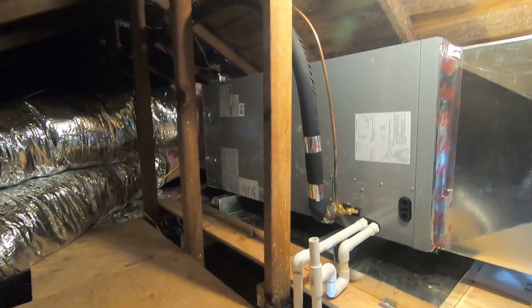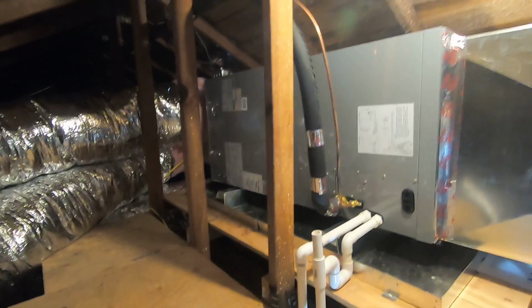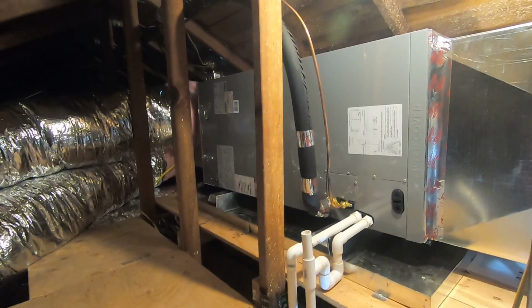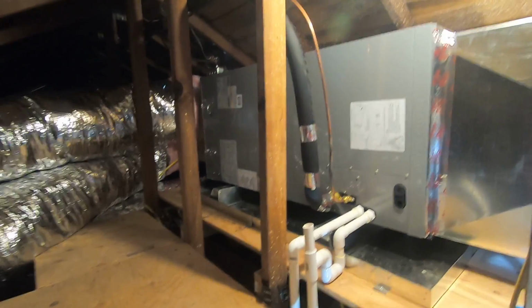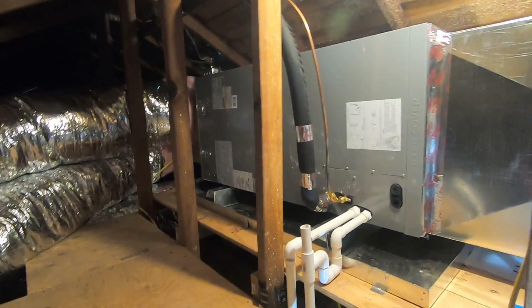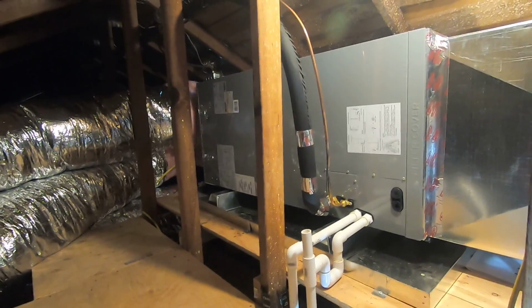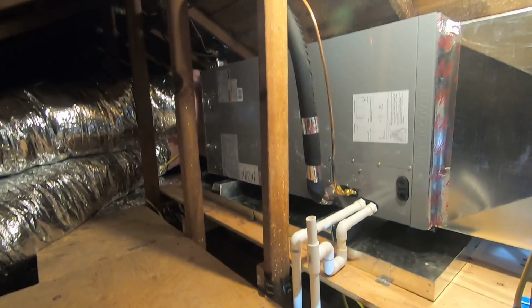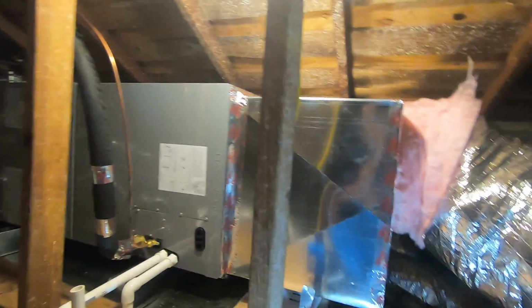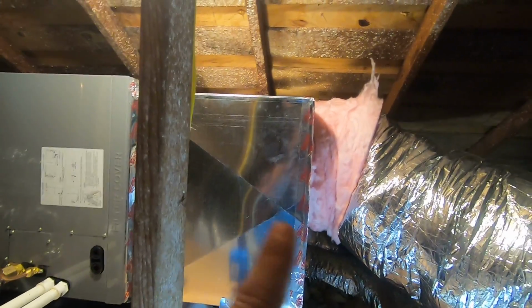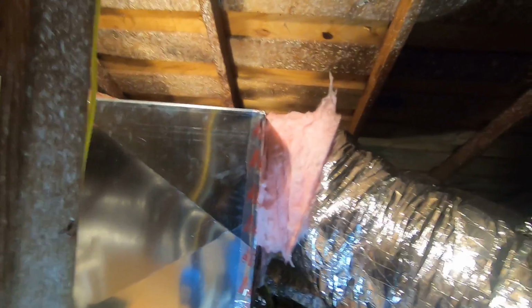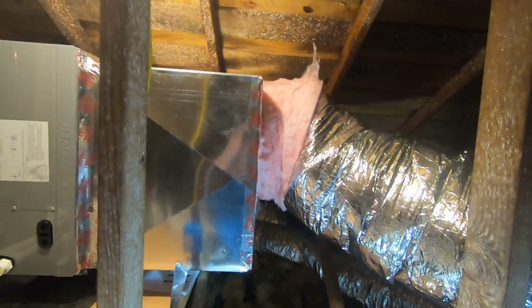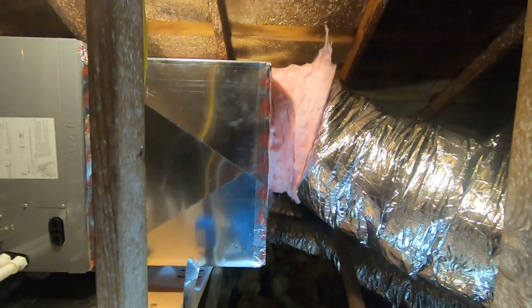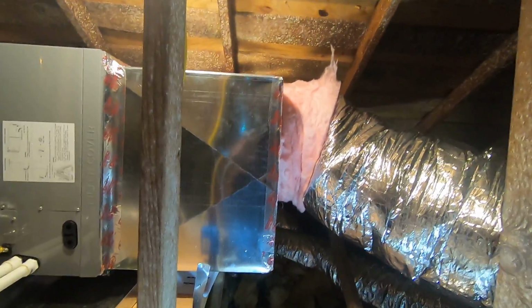So the asbestos came out, very small, undersized stuff, so we upsized everything. We redesigned the ductwork for optimal airflow. It's a 5-ton system, so it puts out up to 2,000 CFMs of air and will pull in 2,000 CFMs of air. So on the back side here we have the return plenum, which is right here. We cut 2 ducts. We have a 12-inch that goes to an office area, which that office is very large, about 400 square feet. It's over a garage and west facing, so we're pulling heat out of that area.